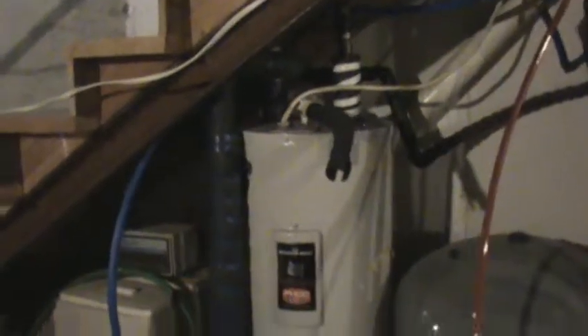Now, if 160 degree water comes out of my tap, I'm going to get scalded. So what I've done, let's see if you can see it. There's an air separator there, and you can't see it very well, but right here is a valve that's a mixing valve, and what it'll do, oh, my heat's coming on. I hope you'll be able to hear me. What it will do is it will actually take the 160-degree water, mix it with cold water, and that way the water that actually supplies the home, which goes through here, will only be at about 120 degrees or so. And what that'll do is increase the thermal mass in this tank because the temperature is so much higher. So I'll have a lot more thermal energy, and basically this small, I guess it's about a 60-gallon tank, will act like it's about a 100-gallon tank, and I'll be able to have plenty of hot water for anything. But I'll still have efficiency, because if there's a case where I don't want to load the boiler, I'm relying on electricity supplying my thermal energy for my hot water, then it'll only go up to 120 degrees and hopefully not be terribly expensive.